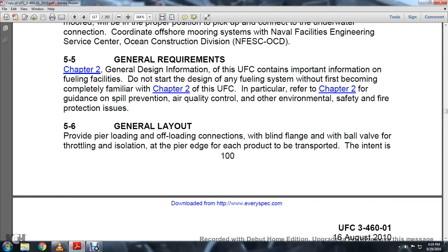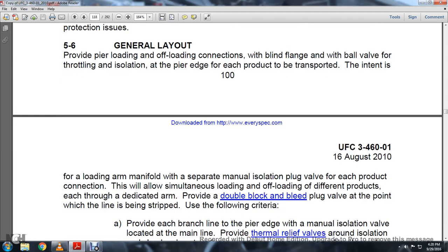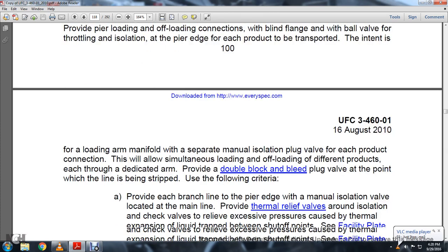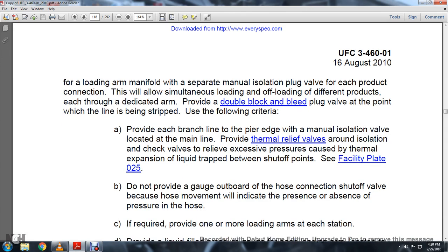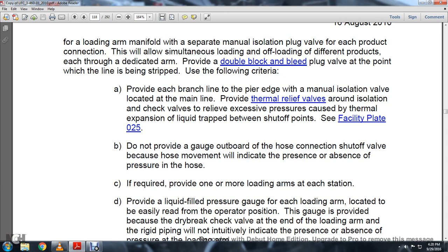Section 5.6 General Layout: Provide the pier loading and offloading connection with a blind flange and ball valve for throttling and isolation at the pier edge for each product to be transported. Connect to the loading manifold with a separate manual isolation plug valve for each product connection. This will allow simultaneous loading and offloading of different products, each through a dedicated arm. Provide a double block and bleed plug valve at the point where the line is to be stripped.